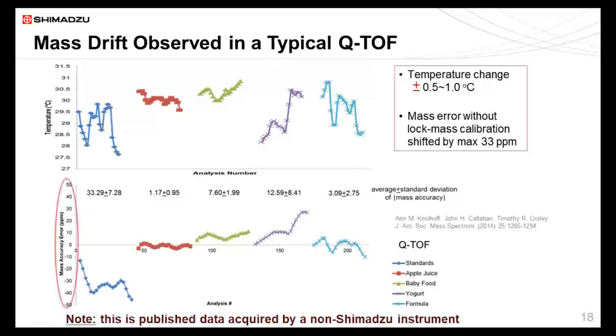So we could see that as the temperature shifts, the y-axis of this mass accuracy error is tens of ppm. So for a temperature change of plus or minus 0.5 to 1.0 degree, you observed a mass error. Without lock mass calibration, it shifted by a maximum of 33 ppm. And you could see that once it shoots off, then it never comes back until quite a while. So this is what conventionally we've been observing and experiencing with the Q-TOF mass spectrometers. And this is why we were thinking that lock mass calibration is a mandate.